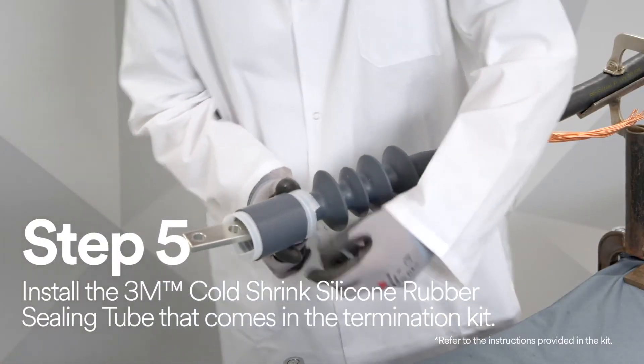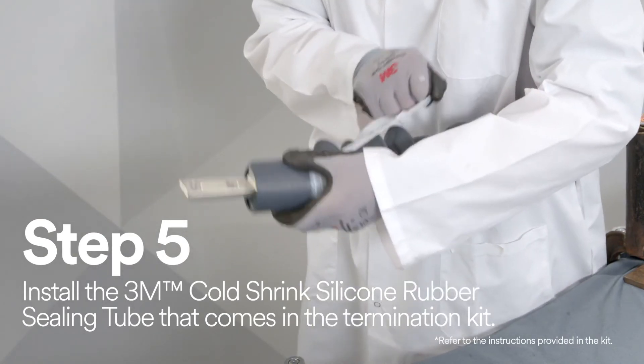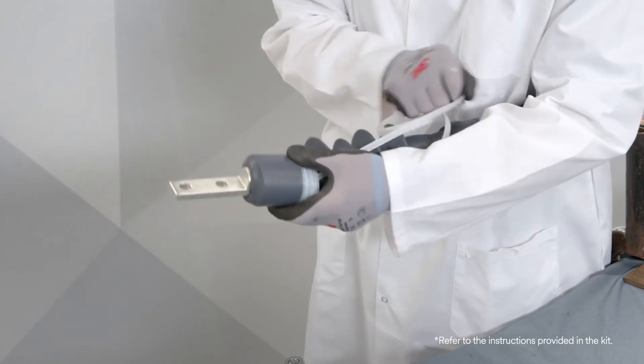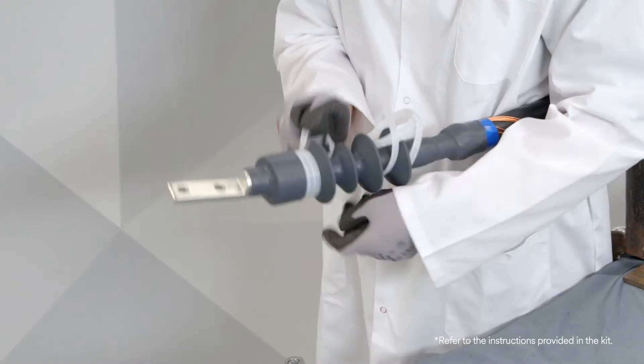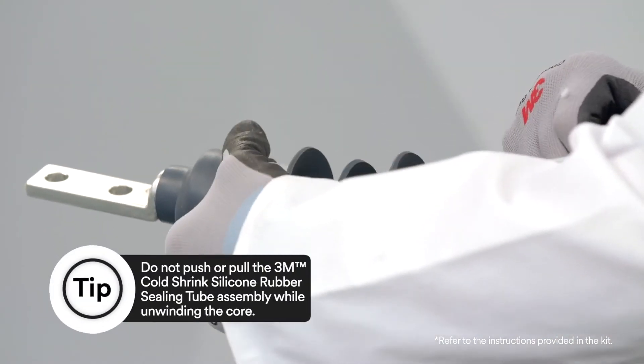Install the 3M Cold Shrink Silicone Rubber Sealing Tube over the foil tape by aligning the edge of the 3M Cold Shrink Silicone Rubber Sealing Tube, not the core, with the lug body edge closest to the connection holes. The loose core end will be facing towards the cable and termination assembly.